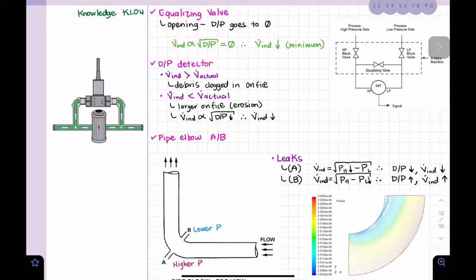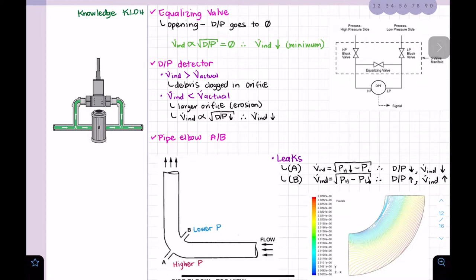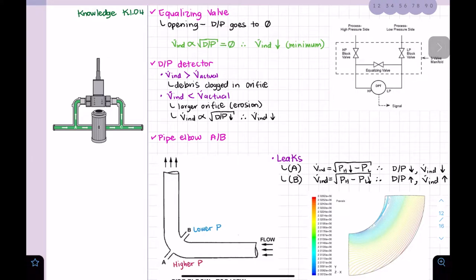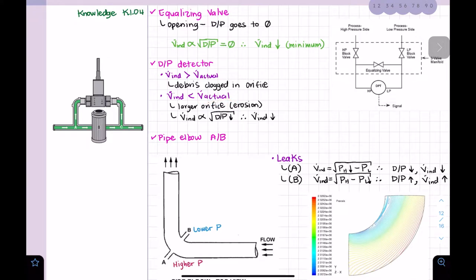If we have a flow indication greater than the actual flow, that means debris is clogged in an orifice. This gives us a smaller area in the orifice, which produces a larger pressure drop and therefore a higher indicated flow. Conversely, when the flow indication is lower than the actual flow, that means the opposite.